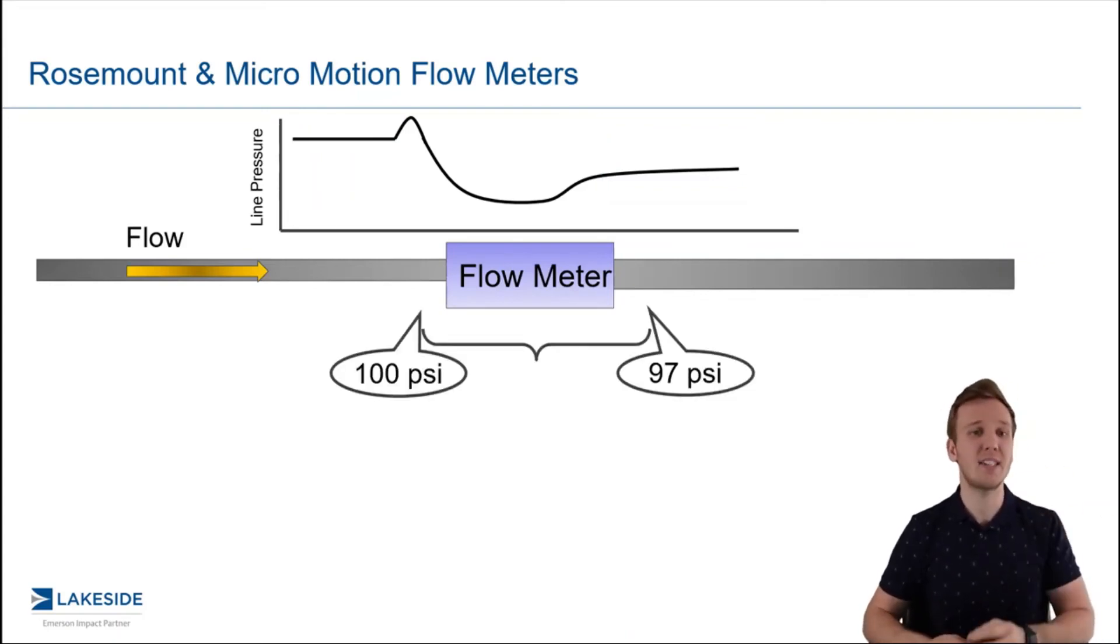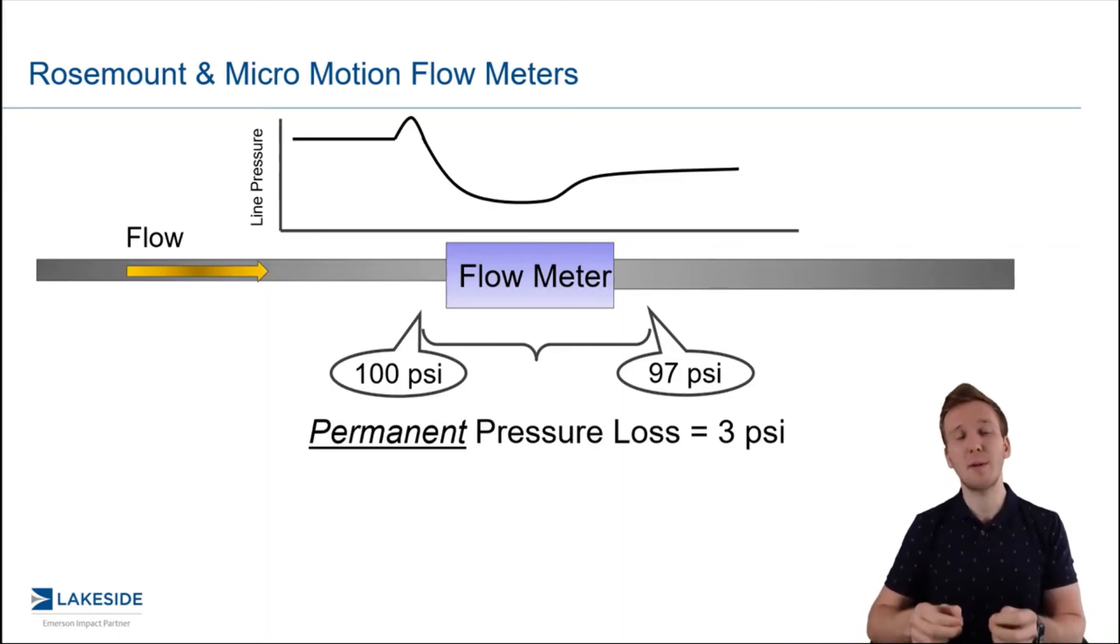So in this case, let's say it's 100 PSI before, 97 PSI after. That means you've lost 3 PSI from this piping system. And this can have a cost impact, especially if it's more significant than 3 PSI, and it's something we need to consider when we're selecting appropriate technologies.